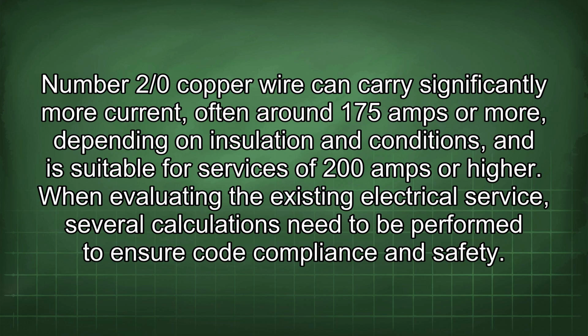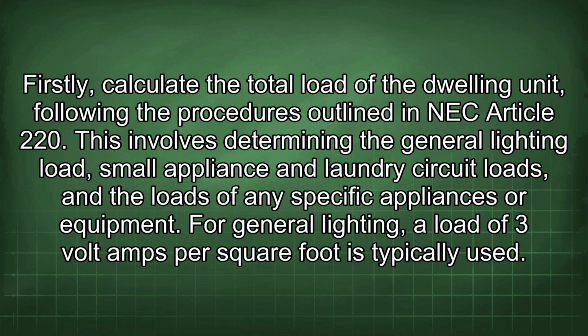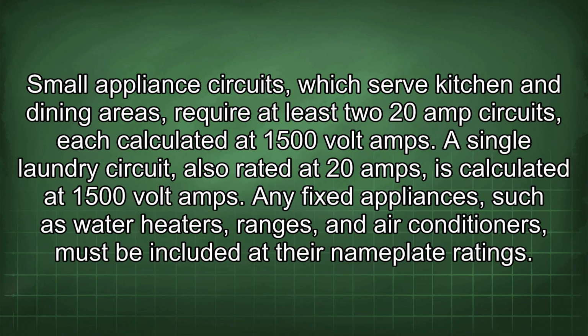When evaluating the existing electrical service, several calculations need to be performed to ensure code compliance and safety. Firstly, calculate the total load of the dwelling unit following the procedures outlined in NEC Article 220. This involves determining the general lighting load, small appliance and laundry circuit loads, and the loads of any specific appliances or equipment. For general lighting, a load of 3 volt amps per square foot is typically used. Small appliance circuits, which serve kitchen and dining areas, require at least 2 20 amp circuits, each calculated at 1500 volt amps. A single laundry circuit, also rated at 20 amps, is calculated at 1500 volt amps. Any fixed appliances, such as water heaters, ranges, and air conditioners, must be included at their nameplate ratings.